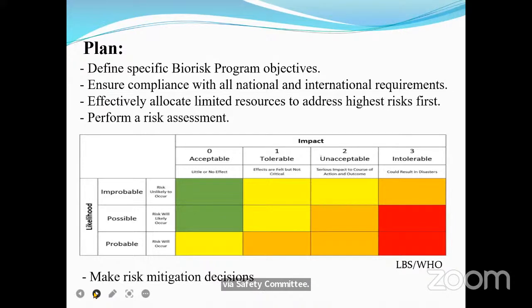One of those methods, which we call the risk matrix, is a common method, used not only for assessing the initial risk but also for ongoing monitoring and review of risk through the life of the BMS. It assesses the initial risk level by measuring both likelihood and total impact if it were to happen, and classifies the risk as intolerable, as you see in the red color.